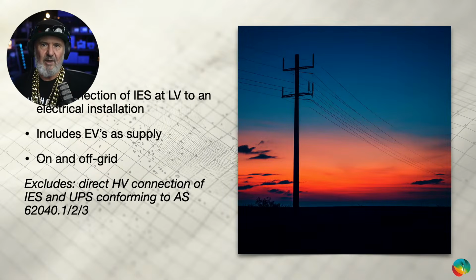We've spent a lot of time trying to solve all the safety issues around that with this standard. And with any scope, there are usually exclusions. An exclusion here is for high voltage connection, so if you're doing a solar farm, for instance, and directly connecting to medium or high voltage, you just need to conform with the DNSP's requirements or the transmission requirements. And if you're installing a UPS system, you need to comply with the UPS standards.